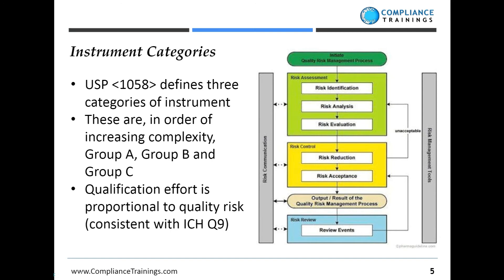The theory is that the less complex an instrument is, the lower the quality risk it poses. Group A is the simplest sort of laboratory instrument; group C is the most complex. The validation activity appropriate to those quality groups varies in terms of complexity. On the right-hand side of this slide I've shown an extract from ICH Q9, which deals with quality risk management. There's an awful lot of what we do these days in the pharmaceutical industry that takes a risk-based approach, so familiarity with this guidance would be incredibly useful.